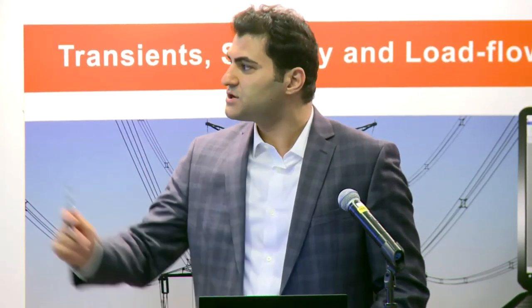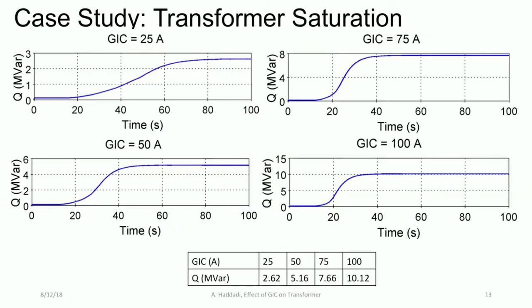Another impact of the increased magnetization current is increased VAR consumption of the transformer. Here are results from a test we performed for a transformer manufacturer, subjecting the transformer to different GIC current levels to see the saturation behavior. Not only are we able to see the steady-state value of VAR, but we can also model the dynamics — the slow build-up of transformer VAR and DC flux. The transformer does not show the same dynamic behavior at different GIC levels, and we are able to calculate that.